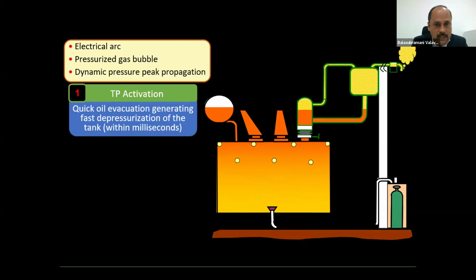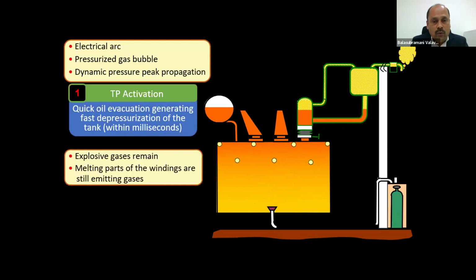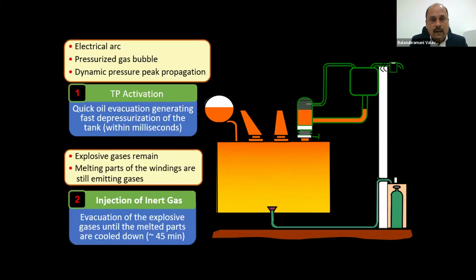Now when this happens, you have to inject nitrogen. The gas will be injected for 45 minutes. The moment it is injected, it will evacuate all the unburned gases, because being an inert gas, it ensures all the unburned gases are taken outside. Upon completion of that, you avoid explosion of the transformer. This kind of system is basically used for transformer protection. Once it is done, you have to recirculate the oil. The moment you recirculate the oil, it is ready for reuse. So this is the greatest advantage of the Sergi system.